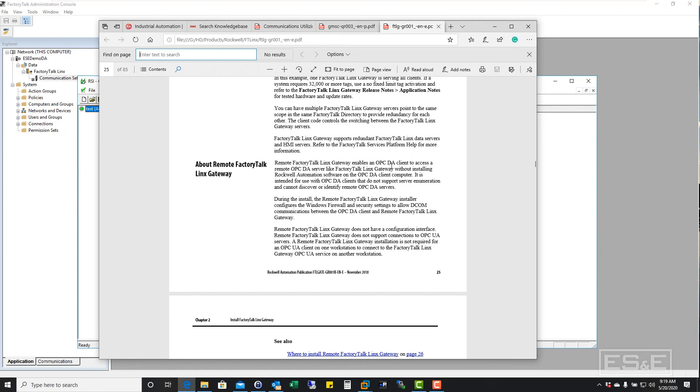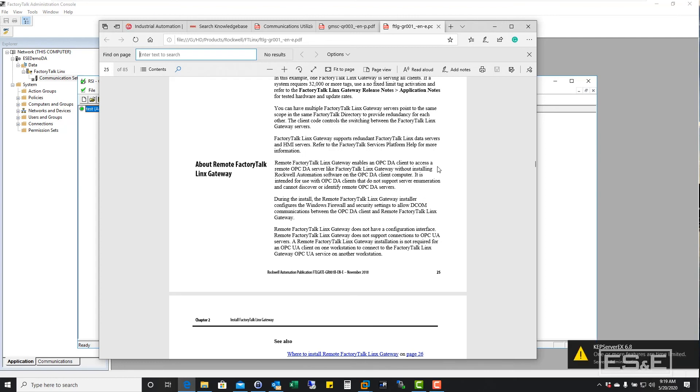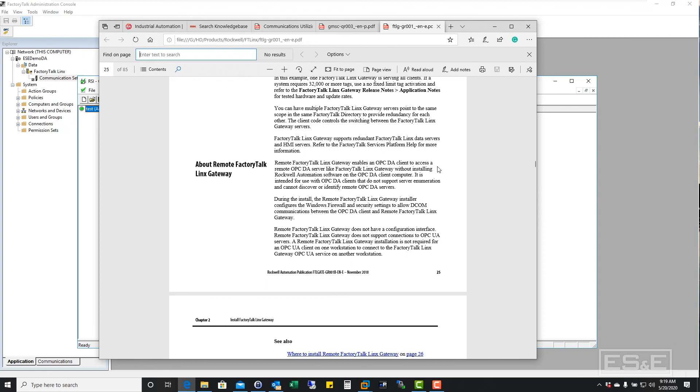You may need to install this remote FactoryTalk Linx gateway. And what it does is enable OPC DA client to access a remote OPC DA server like FactoryTalk Linx gateway without installing Rockwell automation software on the OPC DA client computer. It is intended for use when the OPC DA clients do not support server enumeration and cannot discover or identify remote OPC DA servers. So you may need to install that.